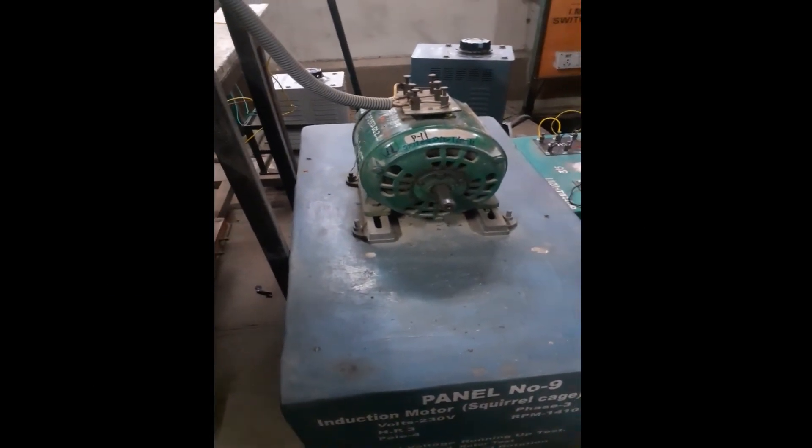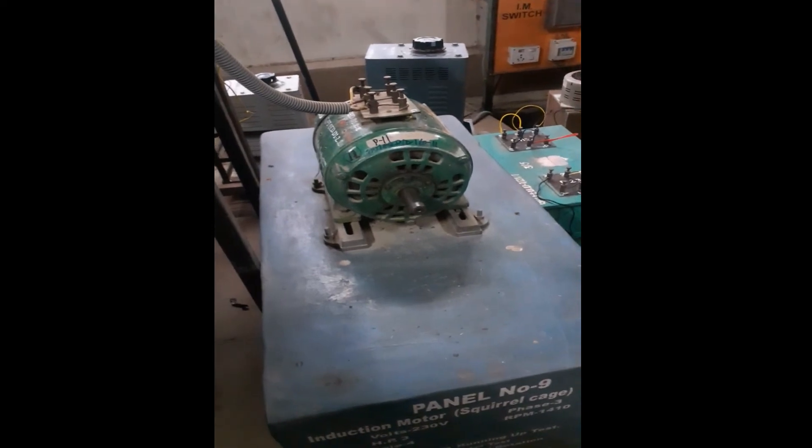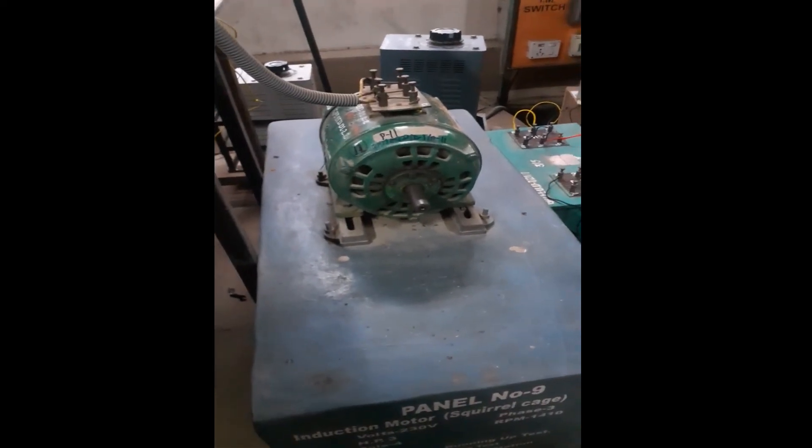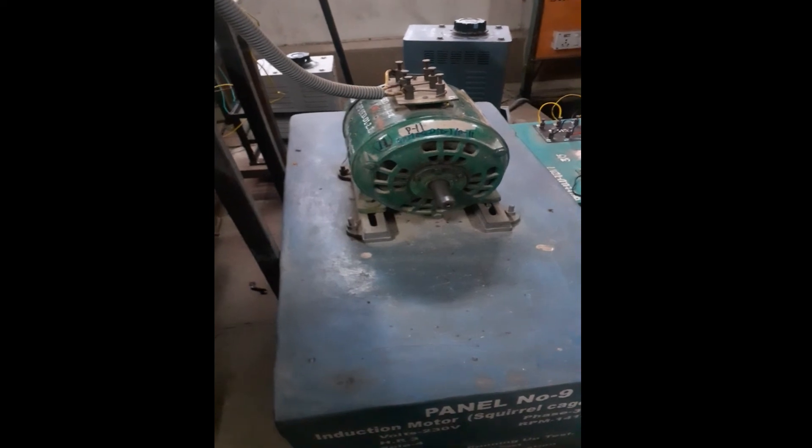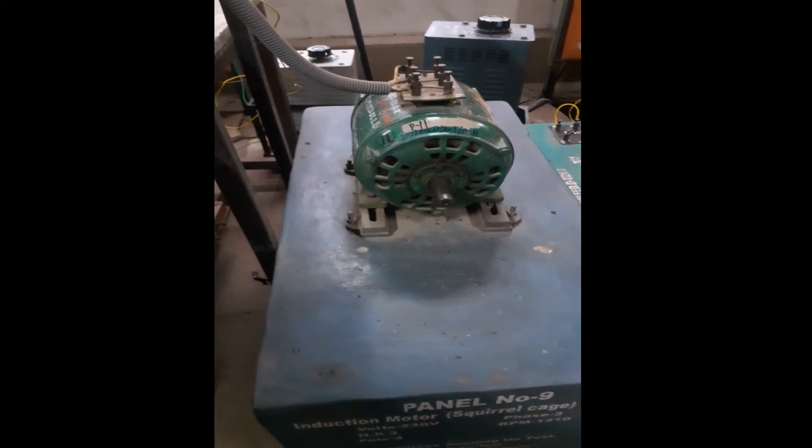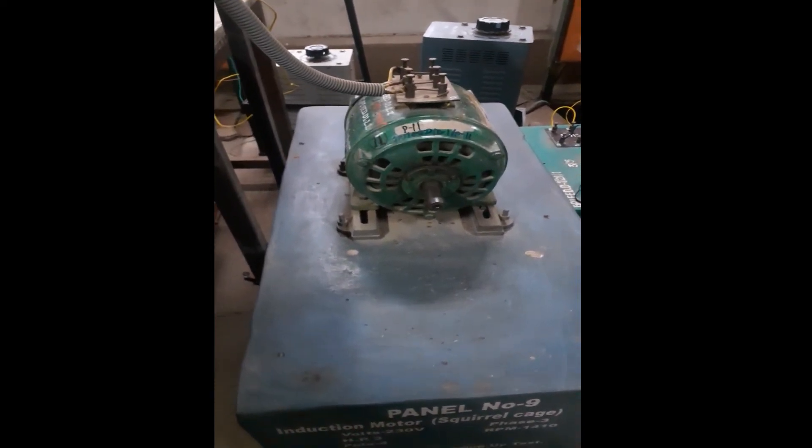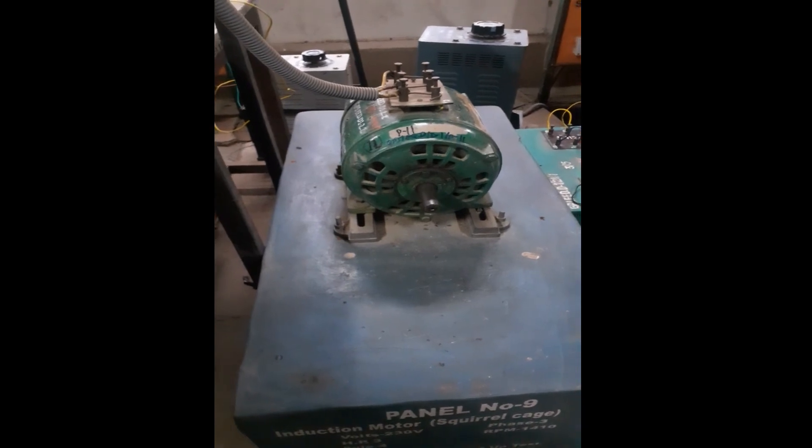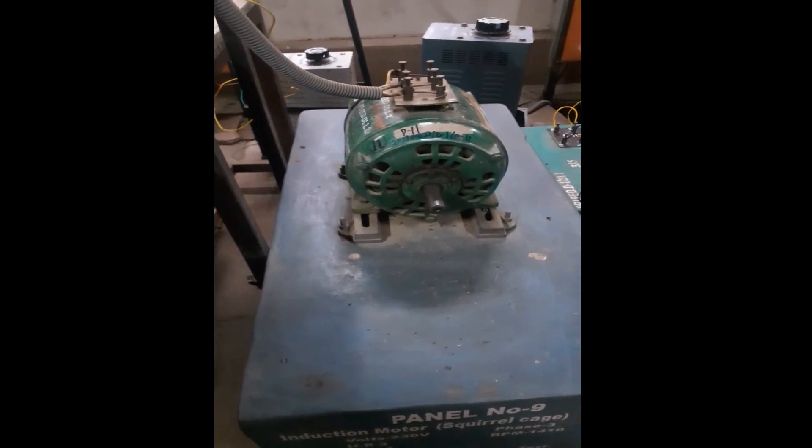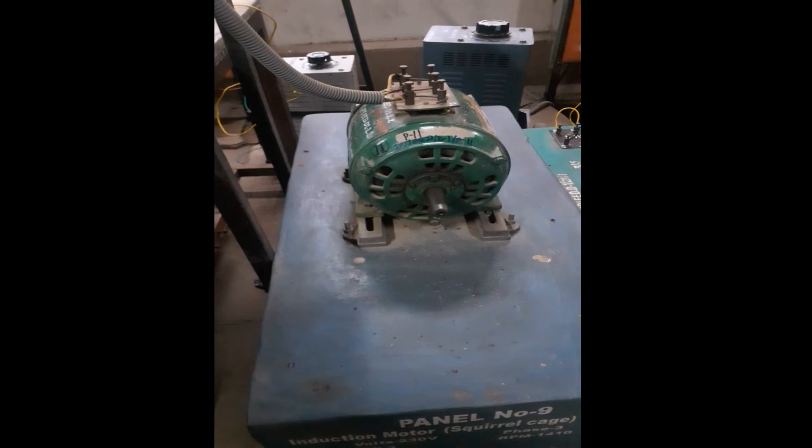This test is performed to know whether cogging or crawling effects are present in that particular motor. If reduced voltage is applied and if 7th harmonic is present in that particular motor, then your motor starts running with lower speed than that of rated value. It is called cogging or crawling.